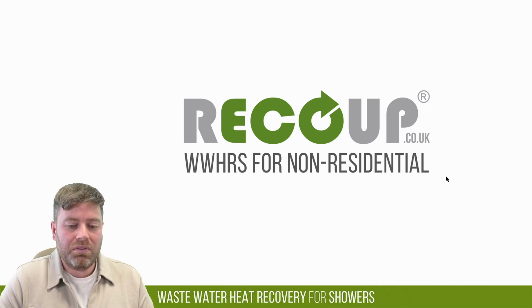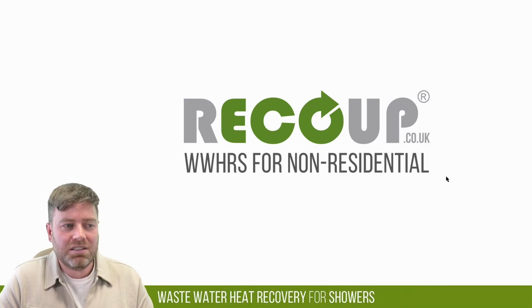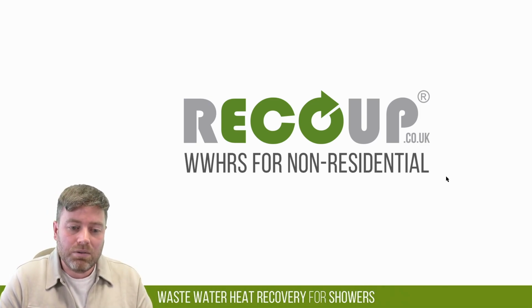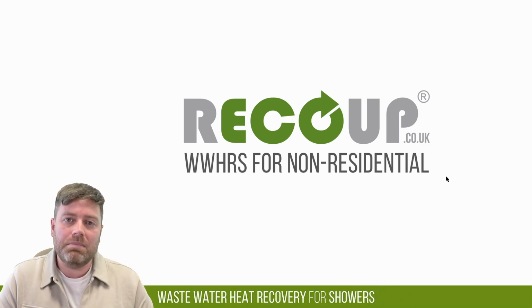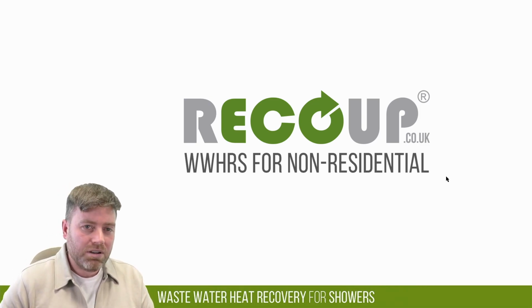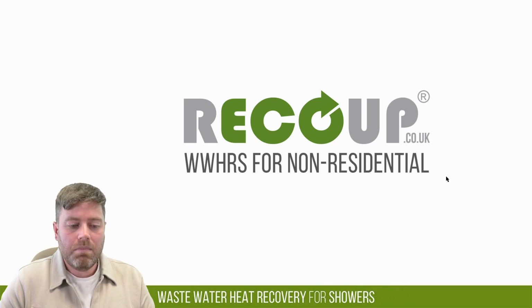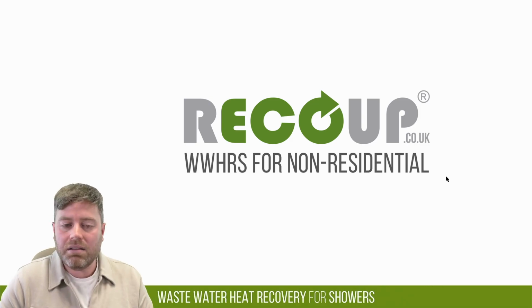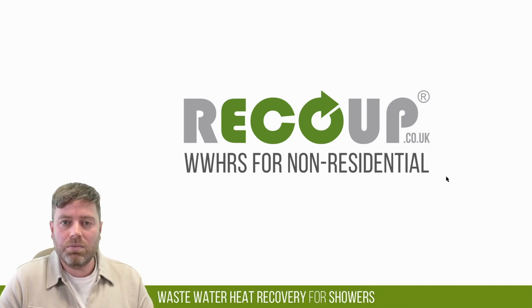It's difficult to quantify exactly how often it needs to be accessed - it depends on use, and Saniflo don't specify a time frame, it's just as required. So in terms of frequency it's hard to say, but the pump element will need to be accessible somewhere, so you'd need an access panel or something. The vertical heat exchanger part doesn't need this though - that's the standard Pipex heat exchanger and can be boxed away as with the regular Pipex. But the pump element does need to be accessible. That's why it's a slight compromise product in a way, because of that pump. It's quite flexible in how it can be designed in though - within a vanity unit with a panel is probably what we normally see.